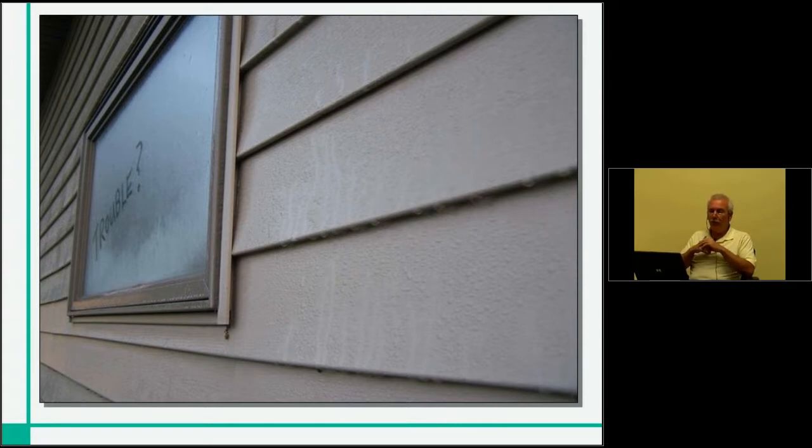Here's the same situation outside — my garage at home where I got up one morning. It was foggy outside on top of the grass. The building was sweating on the outside; it's 60 degrees in the morning. Where did all this water vapor come from? It was there in the afternoon air the day before. The sun went down, took all the heat away. It's air-conditioned inside, so the moisture in the air is now touching a surface cooler than it was the day before — cool enough to reach 100% relative humidity, or its dew point temperature. You can even see the exterior window glass has condensation on it. In the wintertime we see the reverse — condensation on the inside. Understanding this is the key to providing durable, long-term buildings.